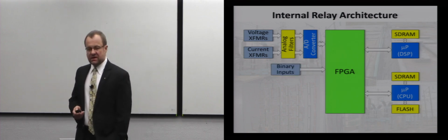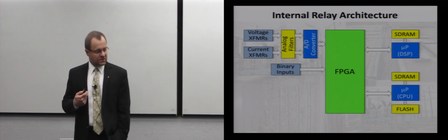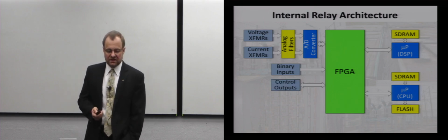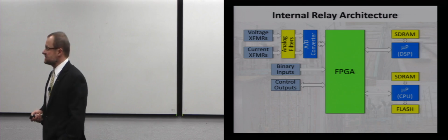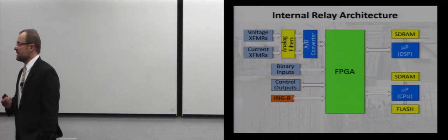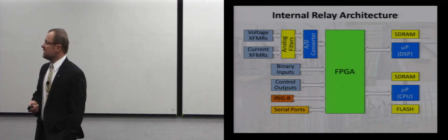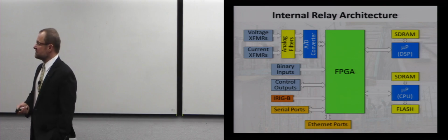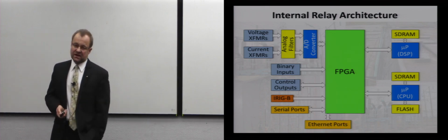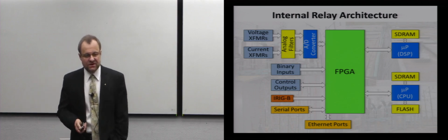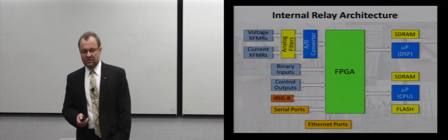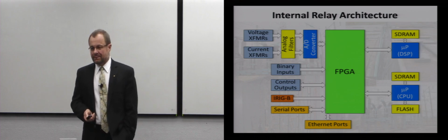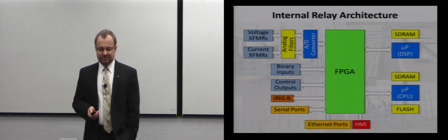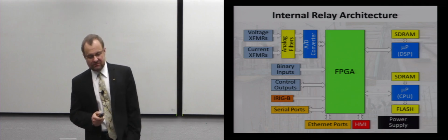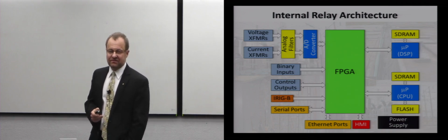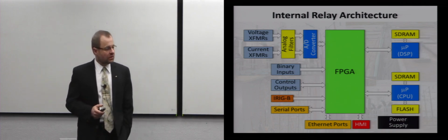I have my binary inputs to get the breaker position or maybe other critical signals. I have to have my outputs. This is how I trip. I may have my IRIG-B for precise timing. I have my serial ports. I have my Ethernet ports that I may route through an FPGA and ask my FPGA to be a simple switch, for example. What else do I need? I need HMI. I need power. I need power to run this stuff. I need probably 80 watts of it to run it.